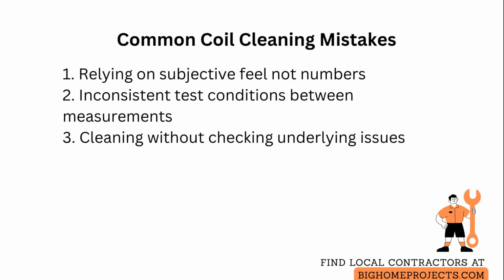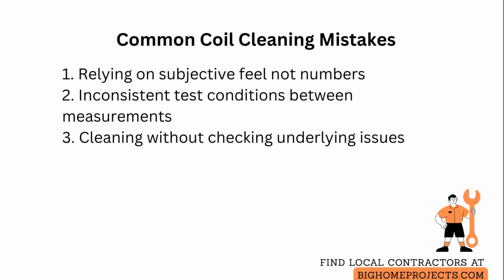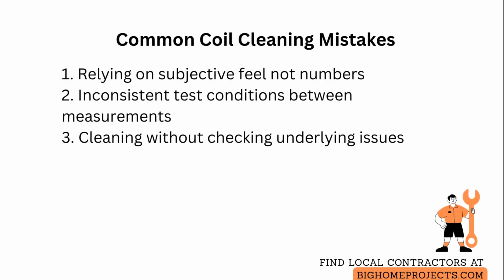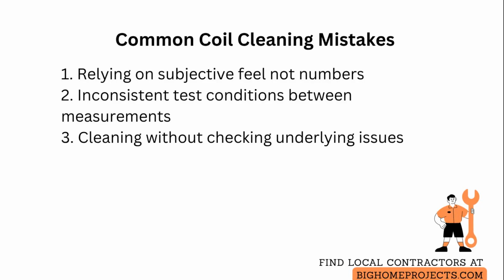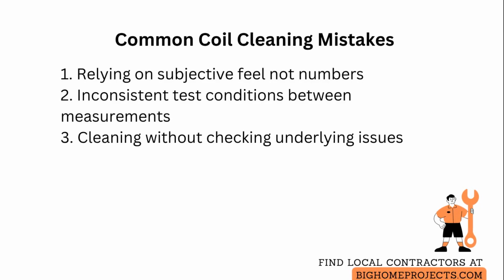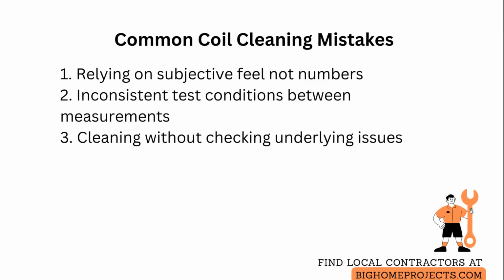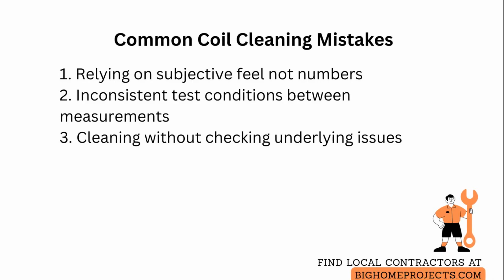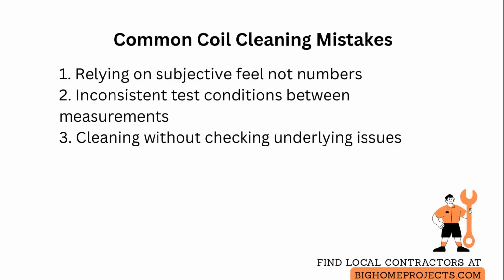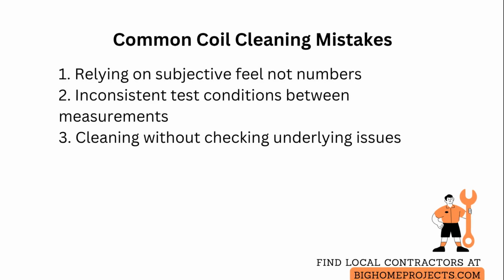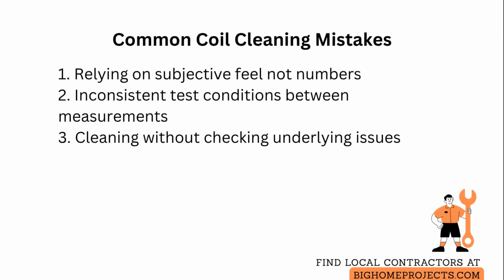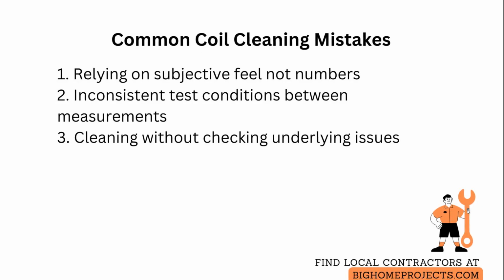Common mistakes include relying on subjective feel instead of numbers, which leads to guesswork. Always document pre- and post-readings so you can show cause and effect. Another issue is inconsistent test conditions, such as ambient temperature or system load changing between tests. So perform before and after checks under similar weather and occupant conditions, or note the differences and correct for them.